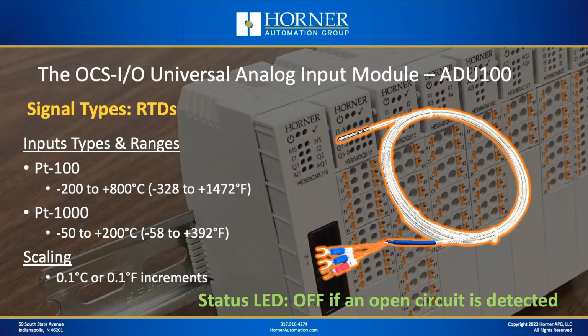Now, from an RTD LED standpoint, if you have an open circuit on your RTD, your status LED on the module will turn off. Something I neglected to mention with 4 to 20 milliamp and 0 to 10 volt: that LED will be on if your reading is above 0, or basically above about 0.2% of 0, in the case of milliamp or voltage.